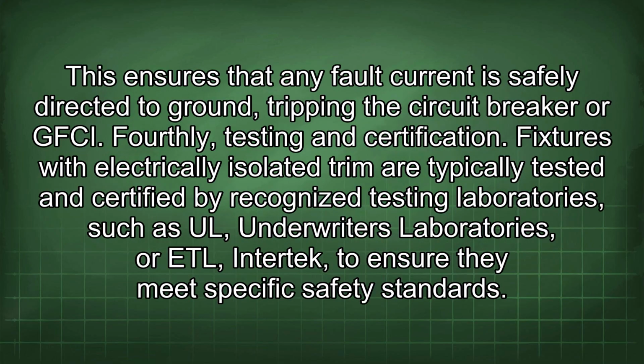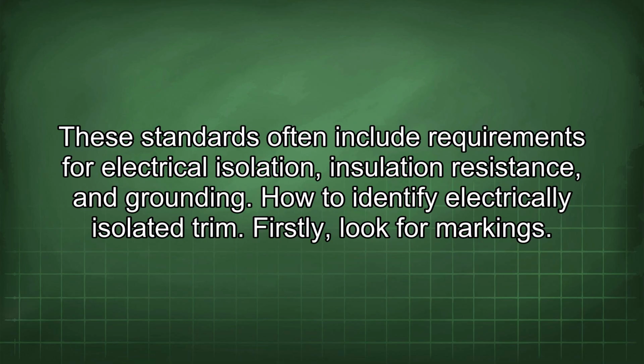This ensures that any fault current is safely directed to ground, tripping the circuit breaker or GFCI. Fourthly, testing and certification. Fixtures with electrically isolated trim are typically tested and certified by recognized testing laboratories such as UL, Underwriters Laboratories, or ETL, to ensure they meet specific safety standards. These standards often include requirements for electrical isolation, insulation resistance, and grounding.